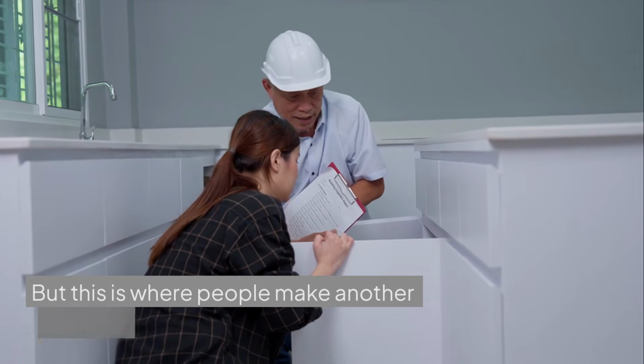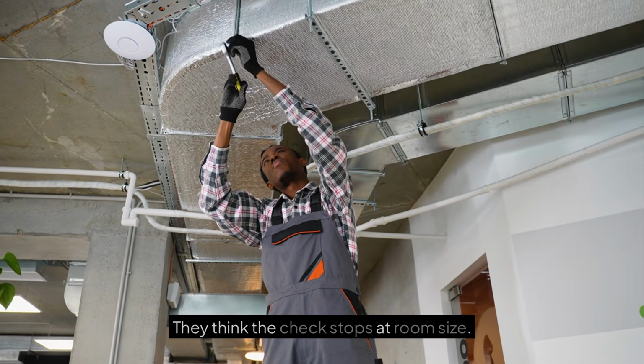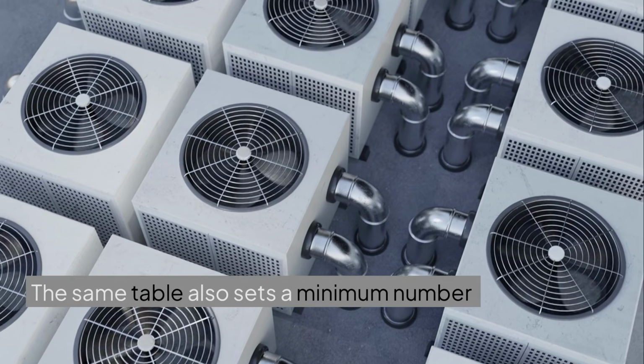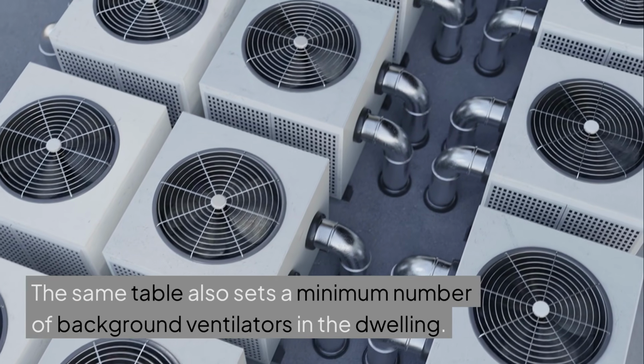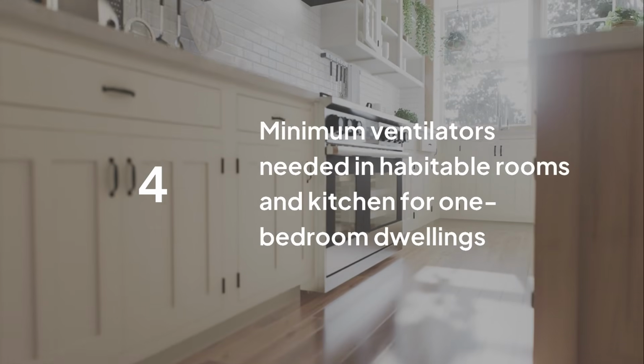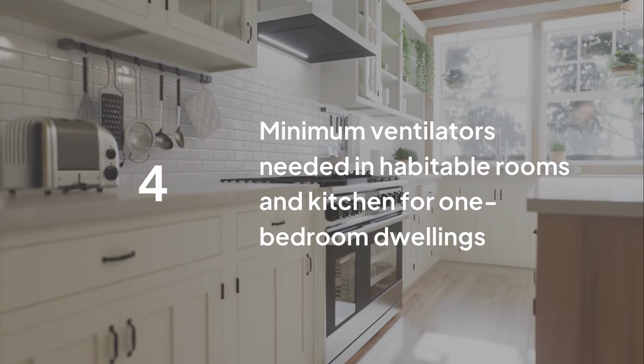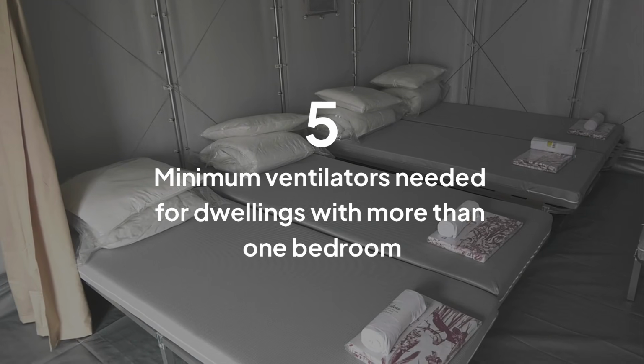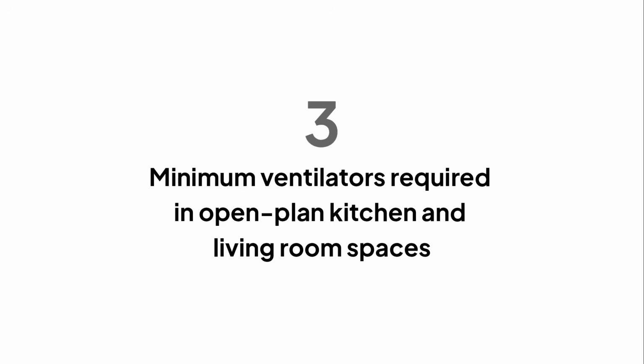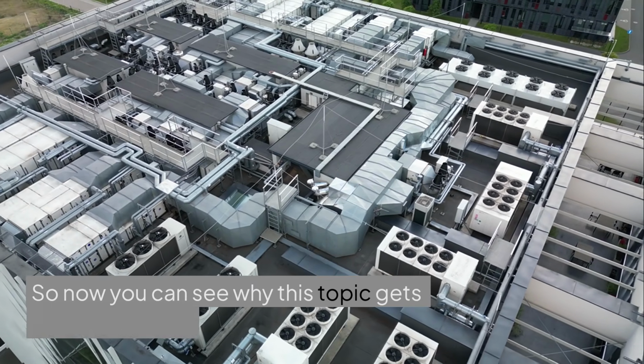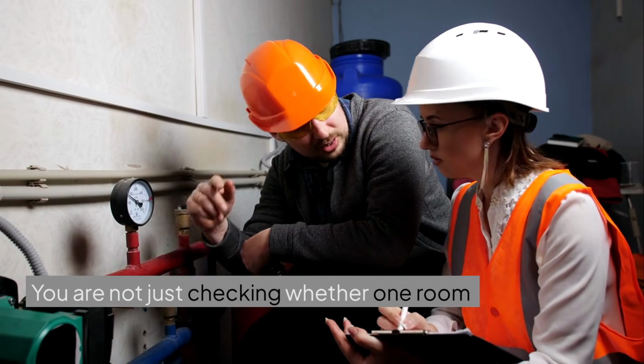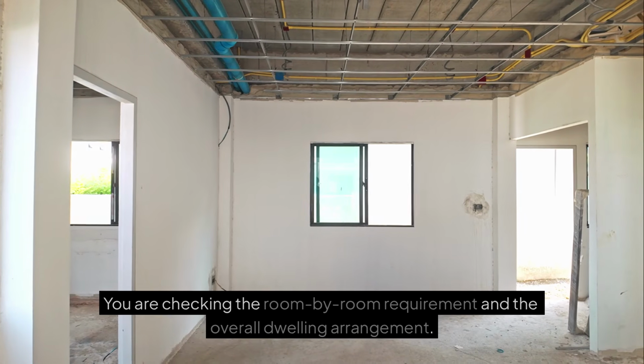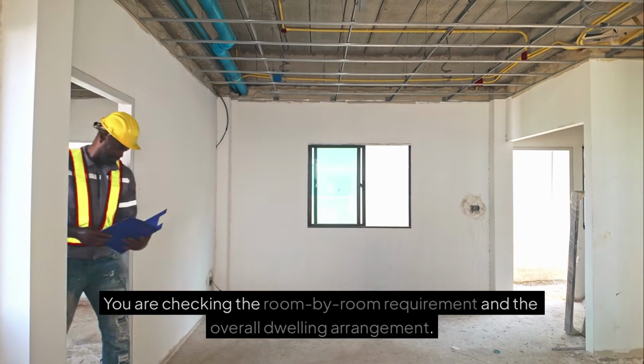But this is where people make another mistake. They think the check stops at room size. It doesn't. The same table also sets a minimum number of background ventilators in the dwelling. A one-bedroom dwelling needs at least 4 ventilators in the habitable rooms and kitchen. A dwelling with more than one bedroom needs at least 5, and if the kitchen and living room are open plan, at least 3 ventilators of the same equivalent area as the other habitable rooms should be provided in that open plan space. So now you can see why this topic gets misunderstood. You are not just checking whether one room has a vent. You are checking the room-by-room requirement and the overall dwelling arrangement.